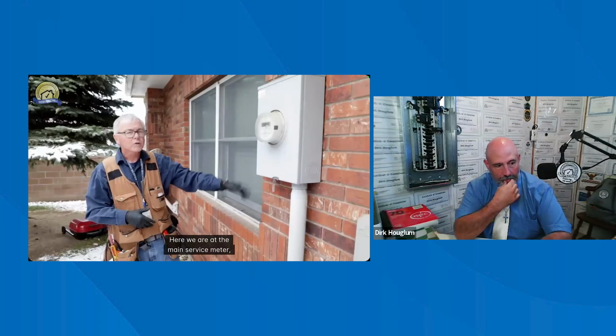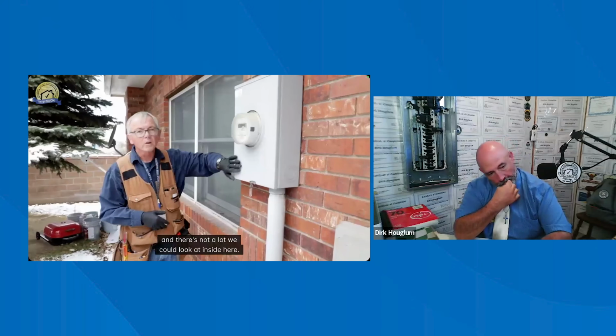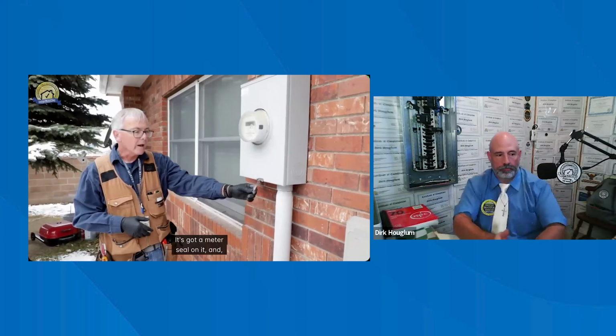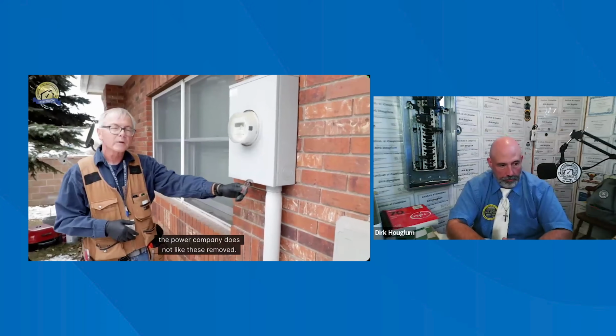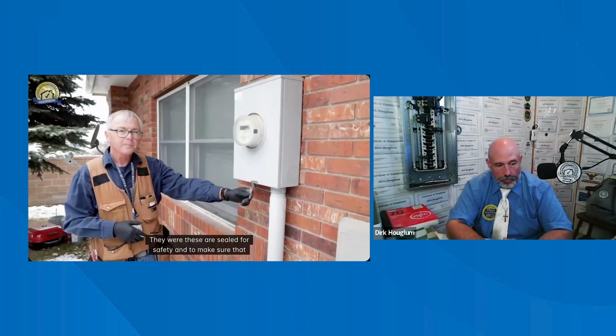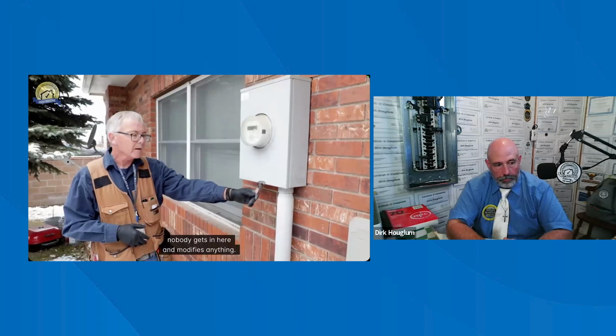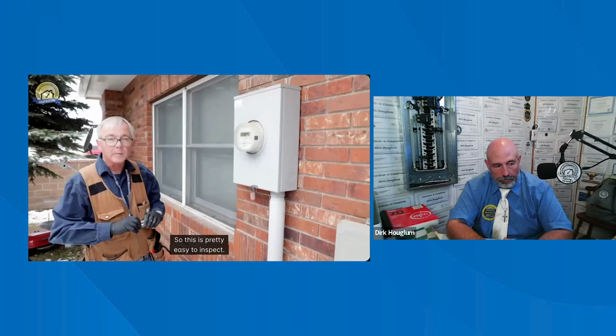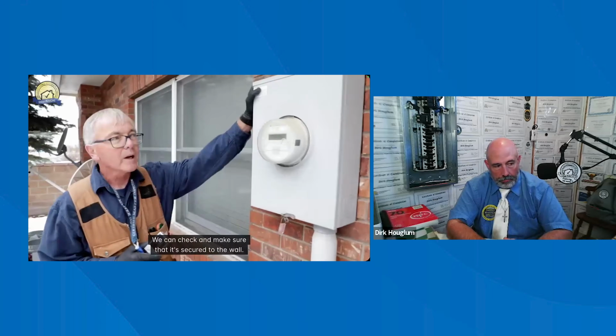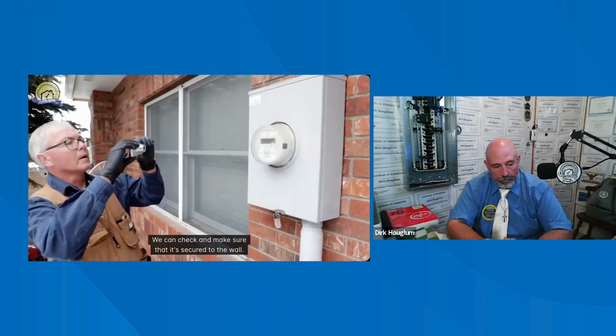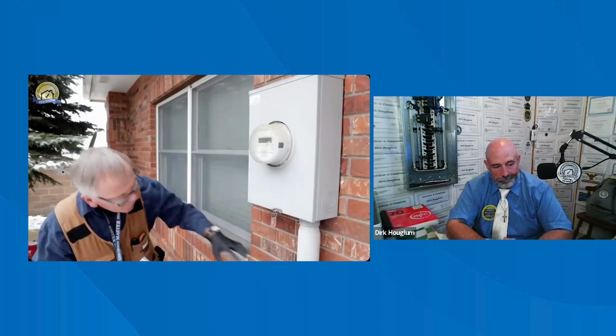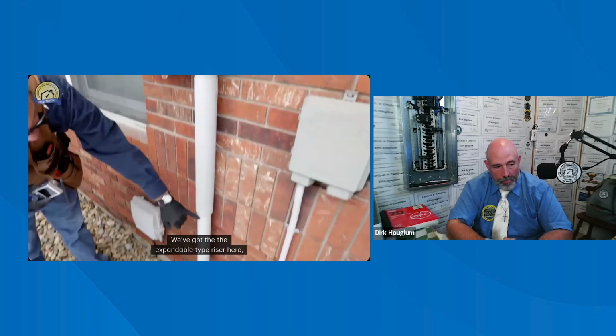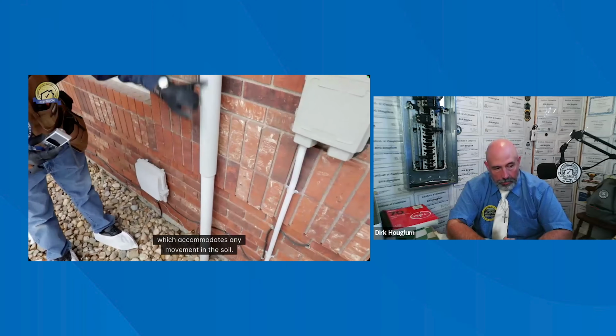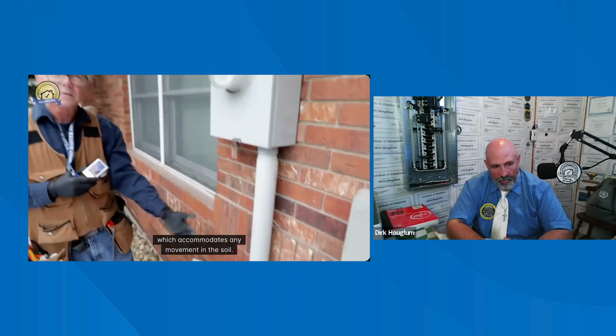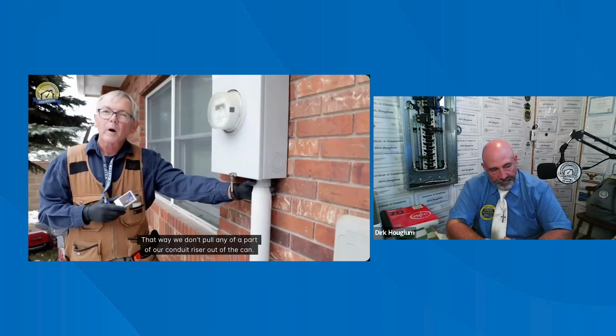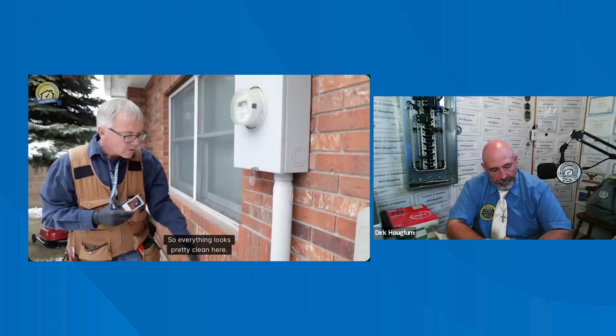Okay, here we are at the main service meter, and there's not a lot we can look at inside here. It's got a meter seal on it, and the power company does not like these removed. These are sealed for safety and to make sure that nobody gets in here and modifies anything. So this is pretty easy to inspect. There's not a lot really we can look at. We can check and make sure that it's secure to the wall. I always like to take a reference photo. Want to check our riser. We've got the expandable type riser here, which accommodates any movement in the soil. That way we don't pull any part of our conduit riser out of the can. So everything looks pretty clean here.